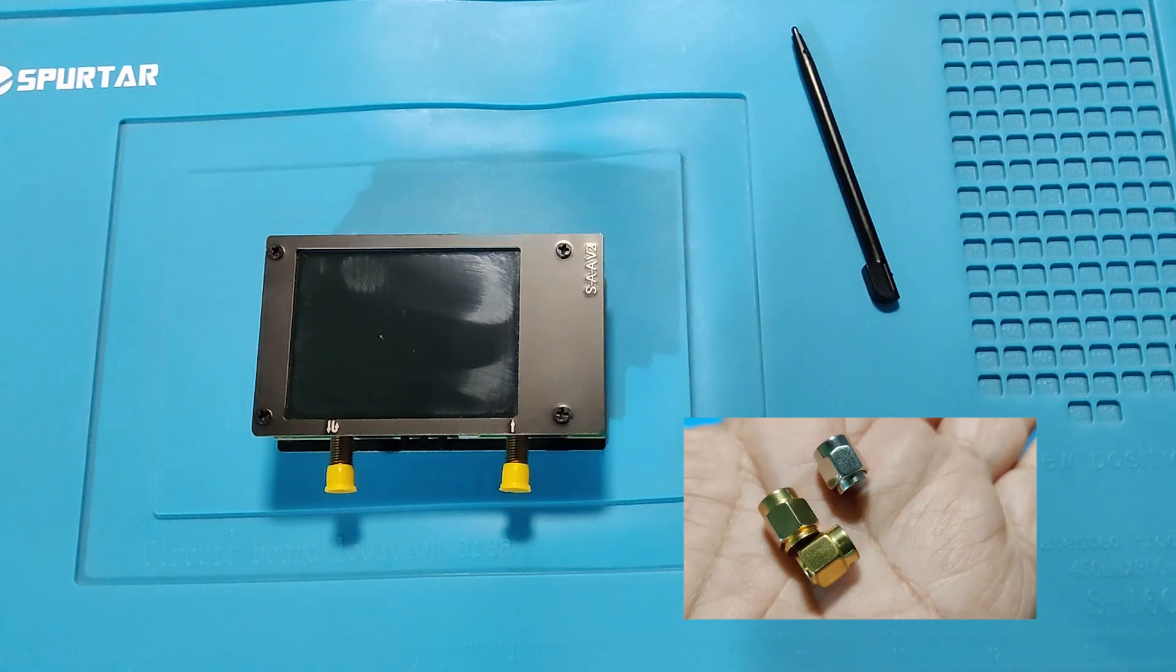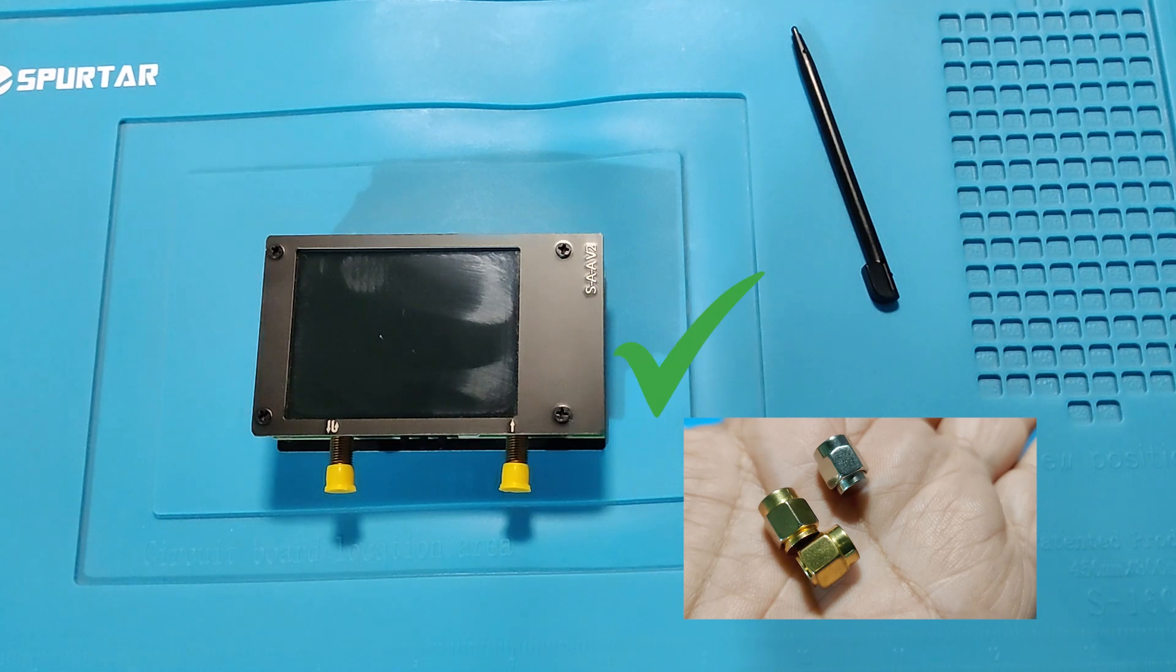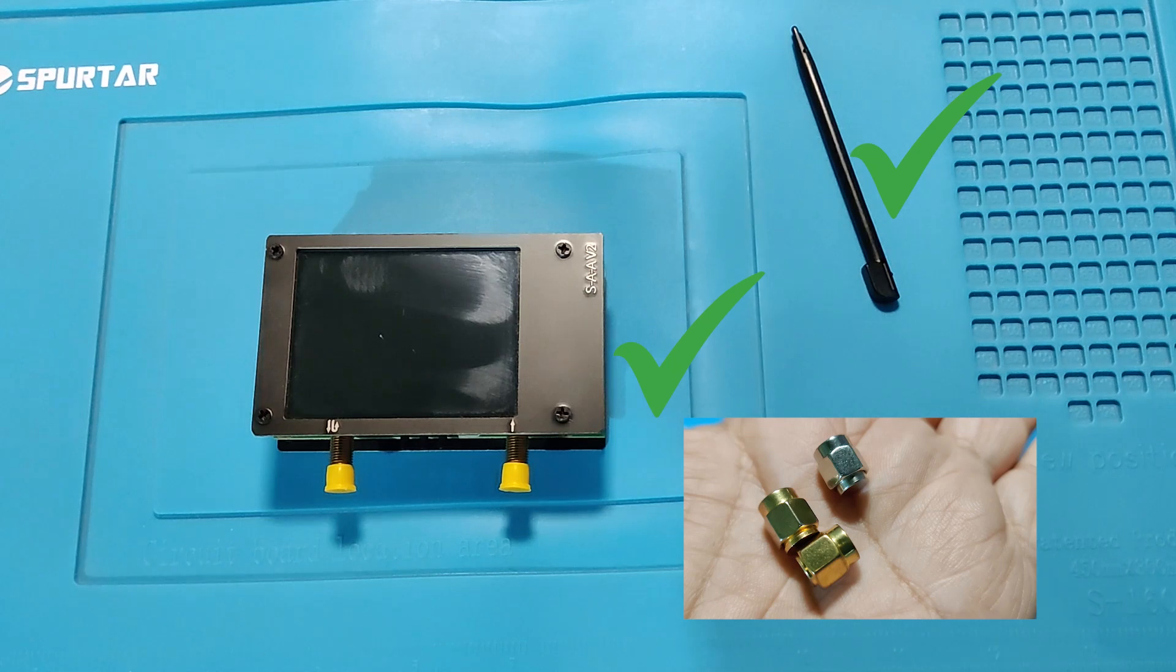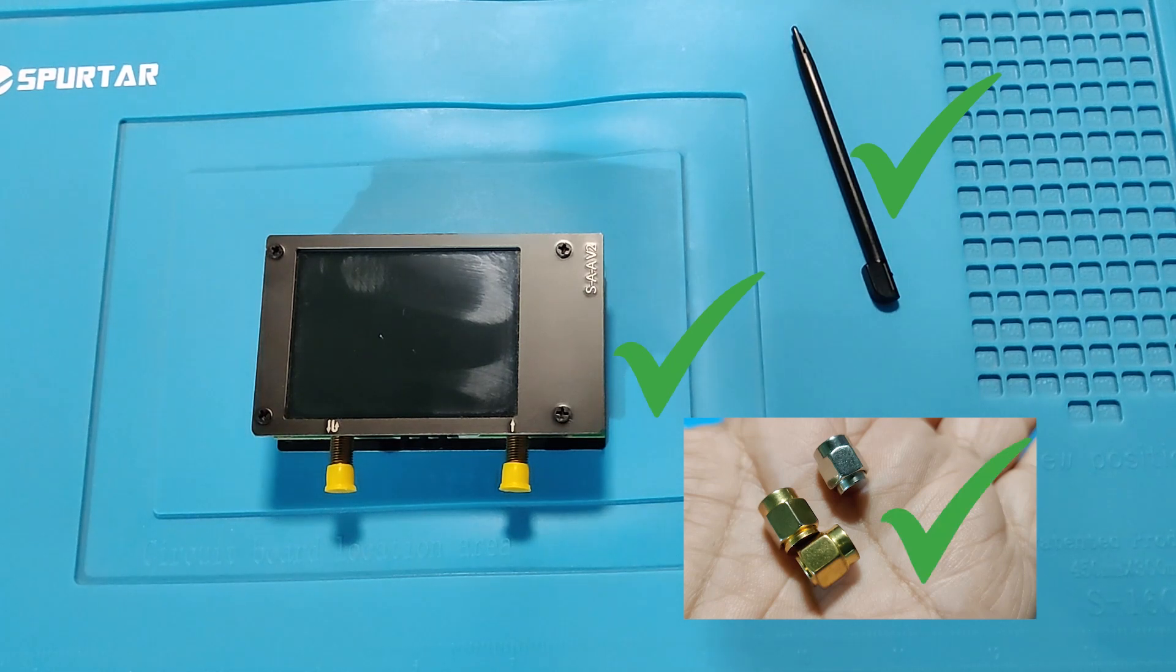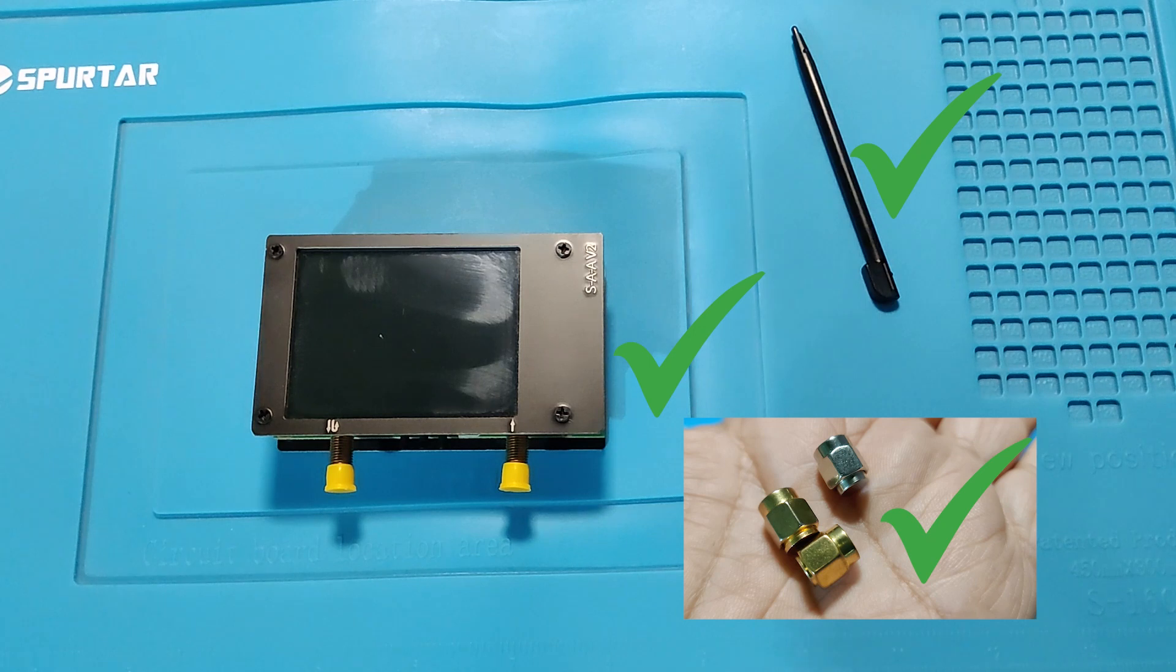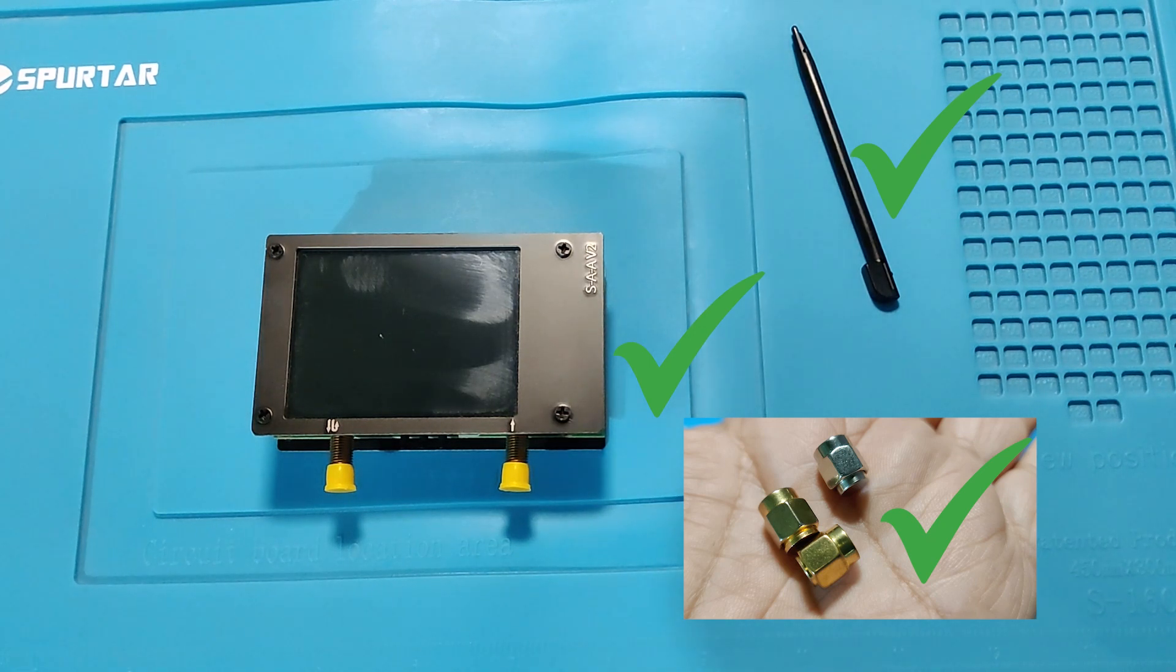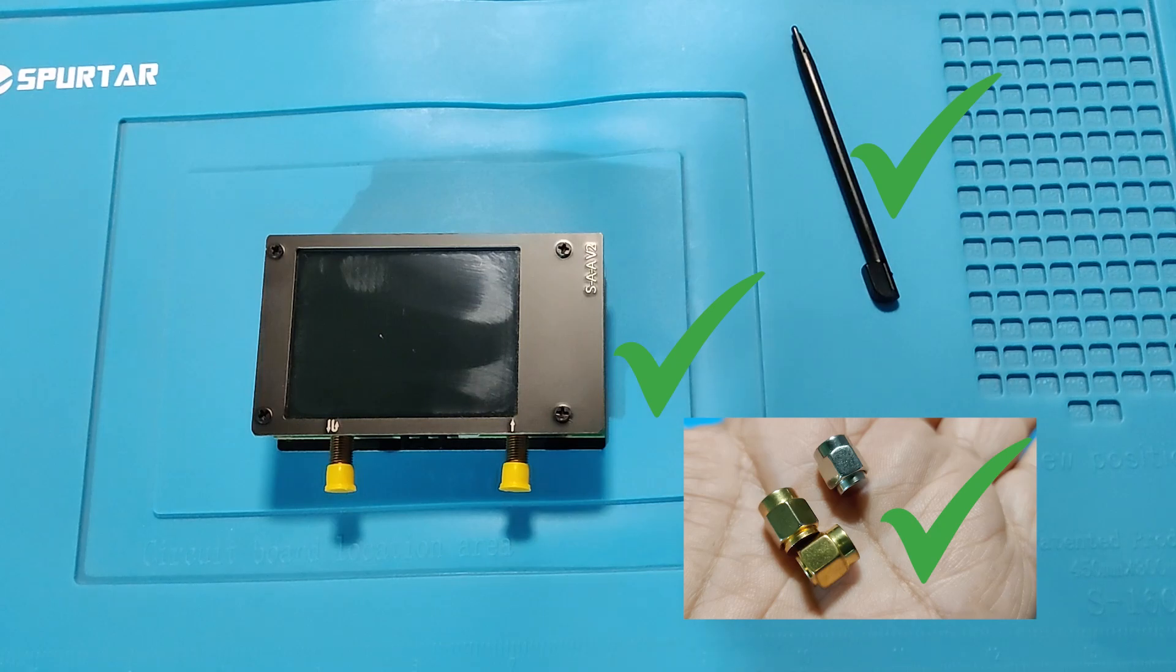To calibrate, we need a VNA, a stylus or anything else to click the screen, and three reference SMA terminators. These are called short, open, and load. We abbreviate it as SOL.